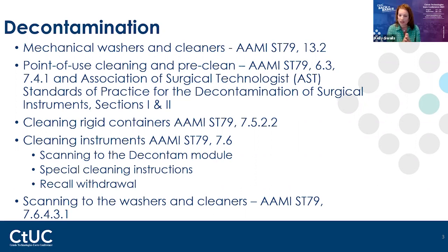So I highly recommend there again that you're looking at your printout tape. I see many times that you have the option to put a roll of tape in there, but most people don't. So put that tape in there, let it print out, result that load, just like you would a sterilizer. Have a document scanner, just like your sterilizer, scan that in, or even better, have it interfaced, and then that tape will automatically be uploaded electronically to that load. So some different options there.